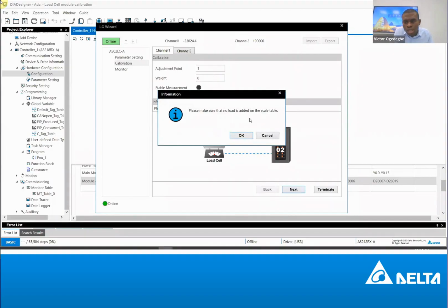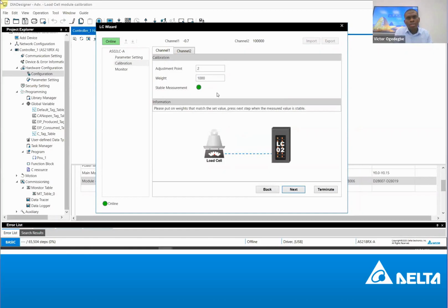If I click next, the wizard will ask you to make sure no load is added. That is true, there's no load added. So now it's stable. You can see that the value has gone to the zero level. Now this is point 2, calibration point 2. In this case, I should put a real weight on the sensor. Let me switch the video. The essence of this is that what the sensor measures, it will give you a correct digital value that you can use in your machine. I switched the video to the module, but I have some error. I think if the error is not cleared, everything may not be perfectly okay. But this is just the principle of how it works. So now you can see the sensor is on the ground there.